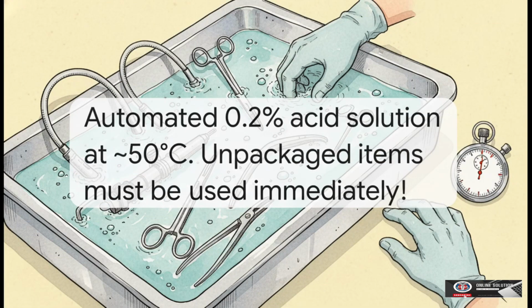The final low-temp alternative is peracetic acid immersion. You're basically giving heat-sensitive, immersible instruments an automated bath in a 0.2% acid solution at about 50 degrees Celsius.